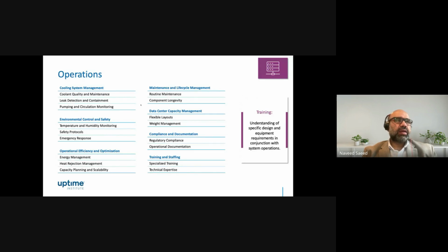And once commissioning is completed, the facility is handed over to operations. And now the challenge starts throughout the life cycle, or throughout the end of life of the data center. Operations teams are the ones who will be handling all the decisions made at the design level and during the construction and commissioning level. So the operations team has to live with them. And most of the time, they don't have much to say when those decisions are being made, but they have to live with those decisions, and they have to make sure that the facility is being operated to the full capacity at the maximum availability once the live IT equipment is energized inside the facility.